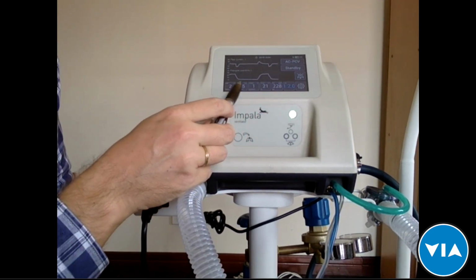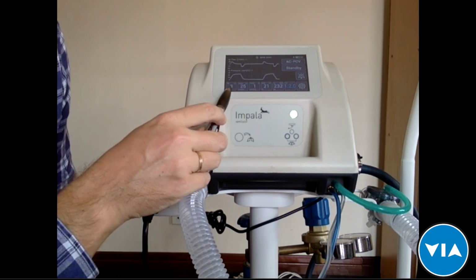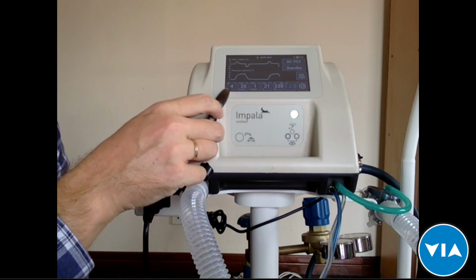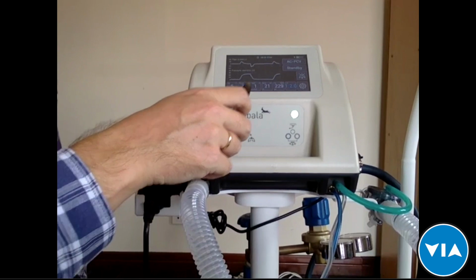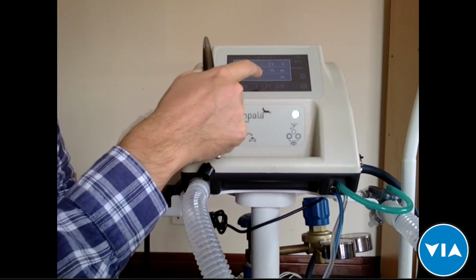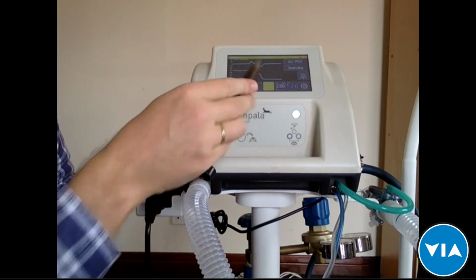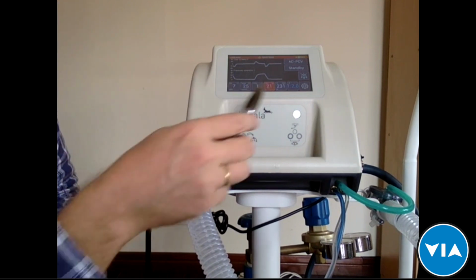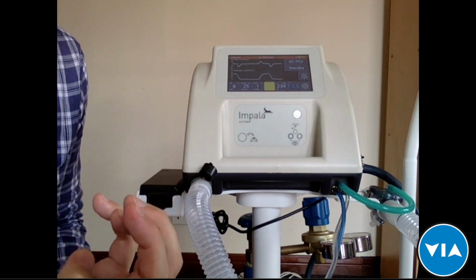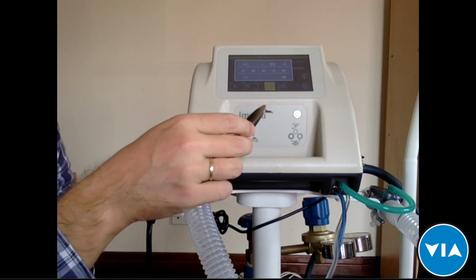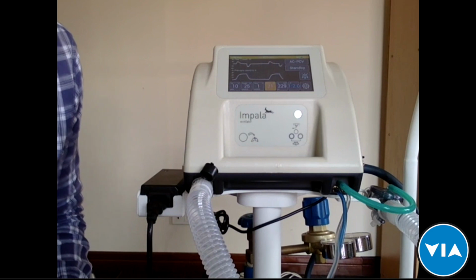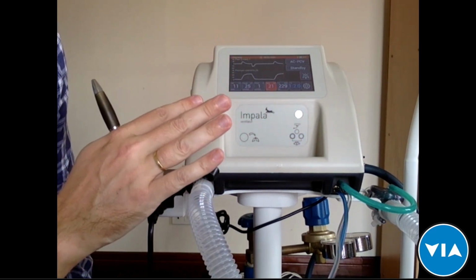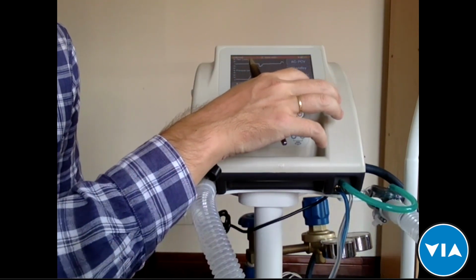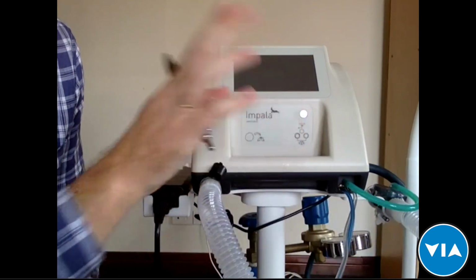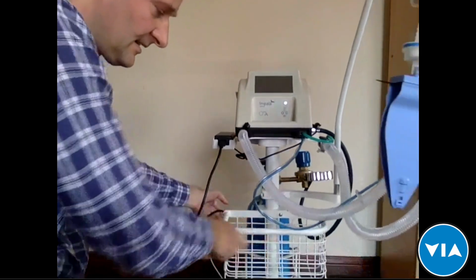So for every number that you can set, it will alarm if for whatever reason the device detects that we are exceeding the set point or we are below the set point. Now let's say I set the oxygen to 50%, which we cannot provide because the oxygen is not connected. Then we're going to have the alarm that there is something wrong with the external source of oxygen, because we set it for 50, but actually we have only 21% of oxygen at the moment. And there are a number of alarms that are difficult to present, but they are related to the failure of the device itself. So I turned it off already, so you know more or less how the alarm is being communicated. And so we have the set point alarms, but also the alarms related to failure of the device.